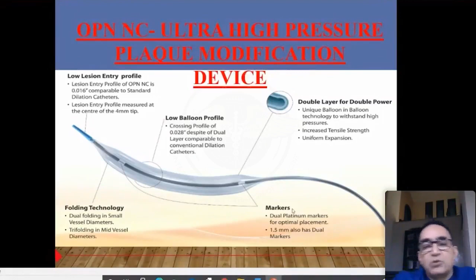But what is more important is this balloon, OPN balloon, can withstand very high pressures. Normally, your rated burst pressure for most of the balloons is around 16 or 12 or 18 or so. And actually, the balloon may perforate beyond 24, 26, 28 in cases of NC balloon. But here, this OPN balloon withstands pressures as high as 45 or even 50. Therefore, this is a very ideal balloon for doing calcified lesions. Calcified lesions where there is a huge atheroma volume and calcification. No matter what you do with your NC balloons, you may not be able to open that.